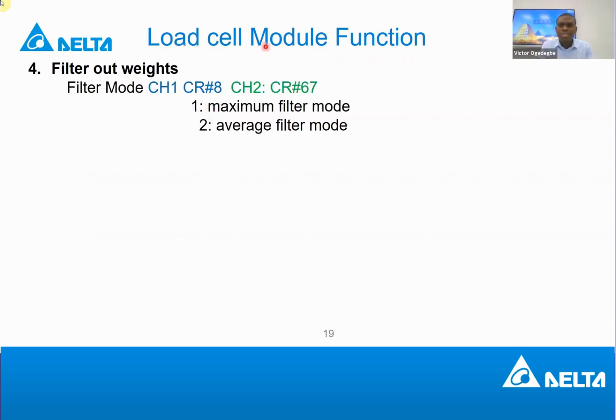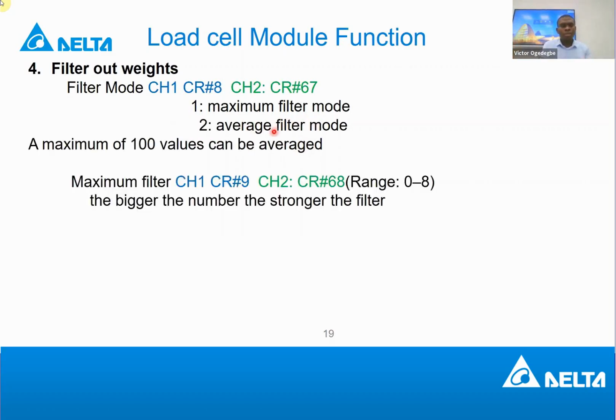So everything in the module has an address. So you can access the address from the control register. All you need to do is specify the control register, use TO to write if the register has a write attribute, or use FROM to read if the register has only read attribute. So in this function, you can choose the filter mode. You can choose maximum filter mode or average filter mode. So it's just like the type of filter. So maximum filter mode filters the maximum measurement so that there's no interruption or noise. And the average filter mode takes several measurements, approximately a maximum of 100 values being measured.